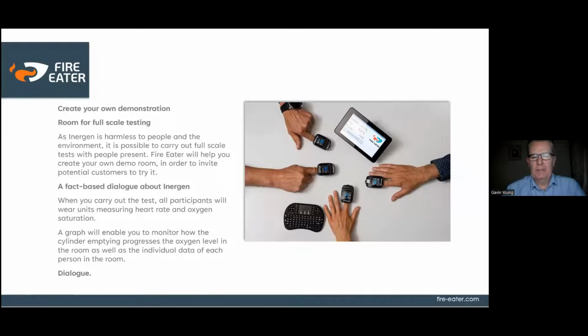We do what we call full-scale testing. You can see the little oxygen meters on those people's fingers there. So we have a room out in Park West where we do live discharges. We start a fire, discharge the gas into the room, and you can see the actual fire extinguished. But also you can stay within that room, and those monitors monitor the oxygen in your blood. It just shows that you can be within the room when the system discharges. It's something that we use quite often, especially on projects with a consultant, for example. We would bring them to show them the proof of the system.